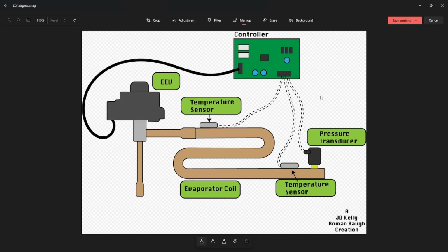When you are checking the resistance of the sensors, you're also going to want to check them to ground. The sensors should not have any continuity to ground. If the sensors have continuity to ground, that means the sensor is shorted, probably somewhere in the wire run. It does happen, and at that point, you're going to need to replace the sensors. The sensors are on a shared Molex connector that plugs into the board, kind of like it shows right here. So if one's bad, you've got to replace them both. It is what it is.